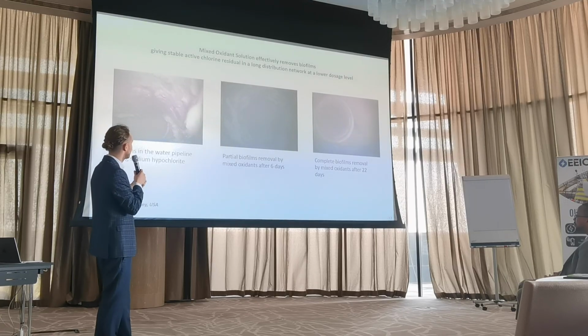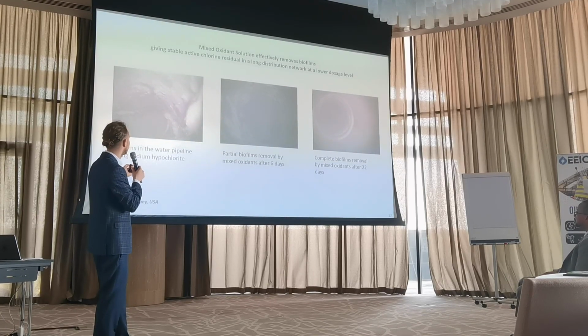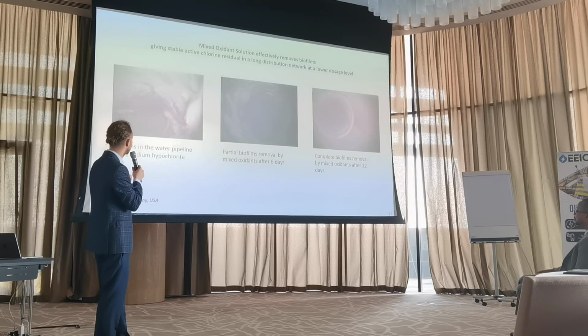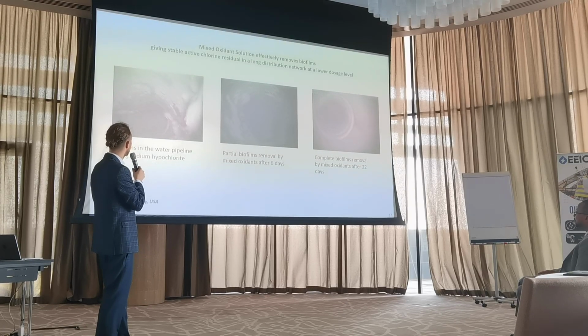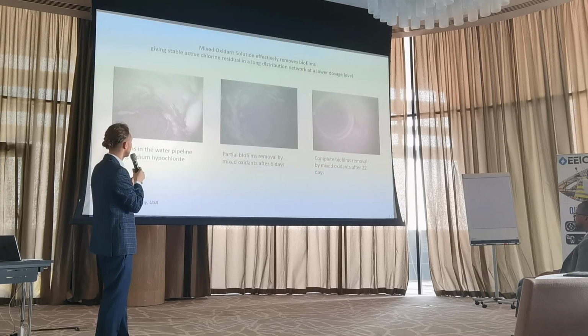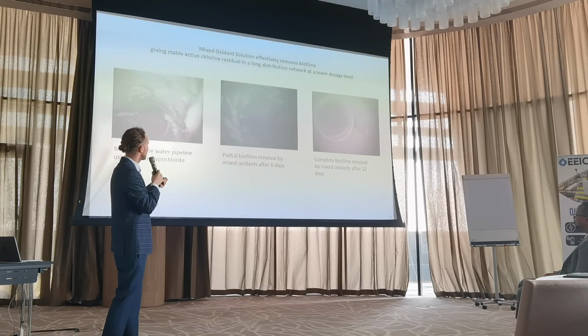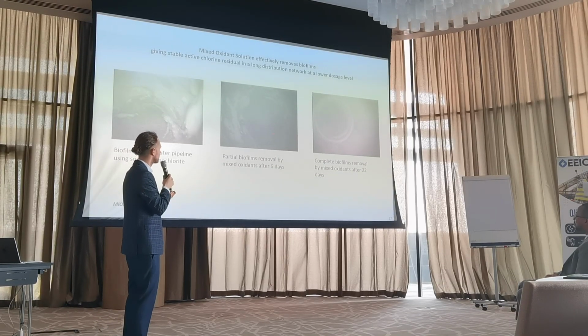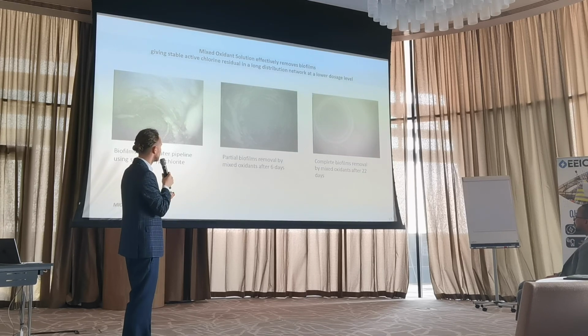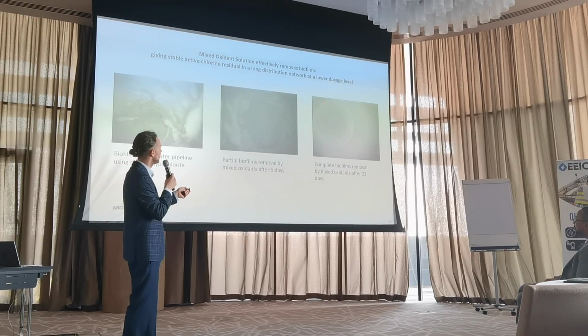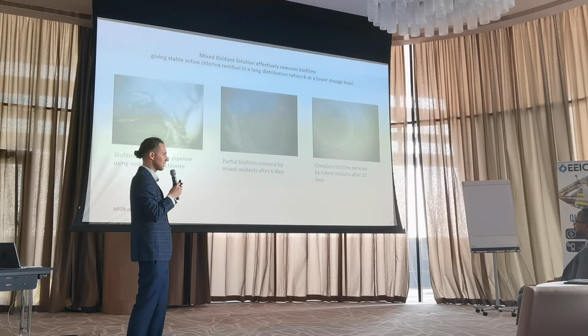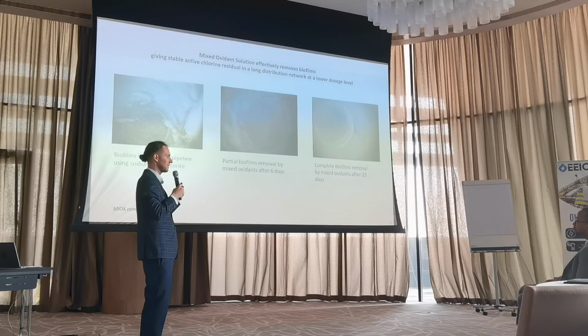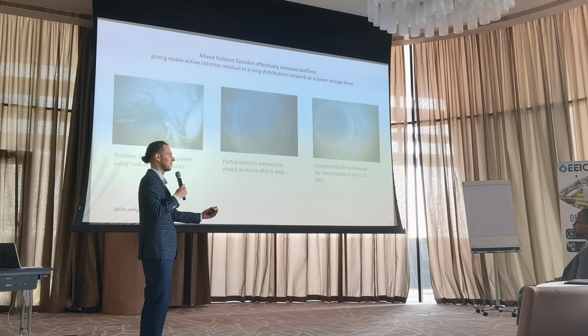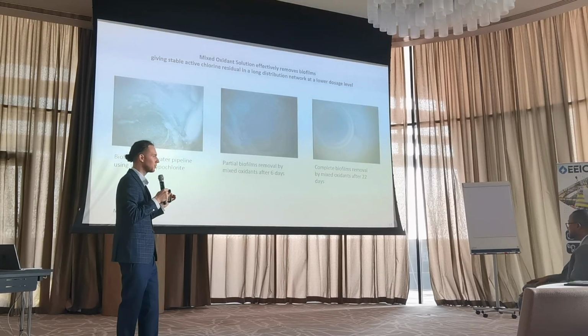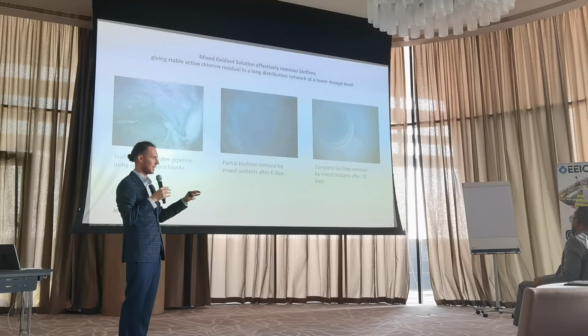These photos aren't very good because they were taken inside the pipes. This is a wastewater treatment plant in the USA. This was the pipe condition with sodium hypochlorite. This is after 6 days once we started dosing 8 ppm of mixed oxidants, and this is after 22 days. The pipe was cleaned, and that's one of the most important reasons why we give better active chlorine residual, because with this solution you can really clean your network.